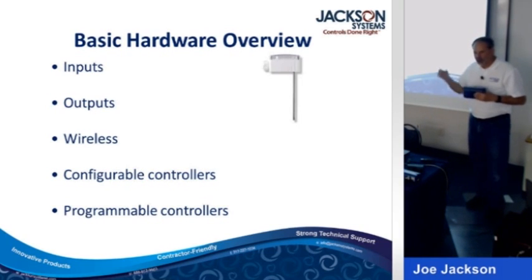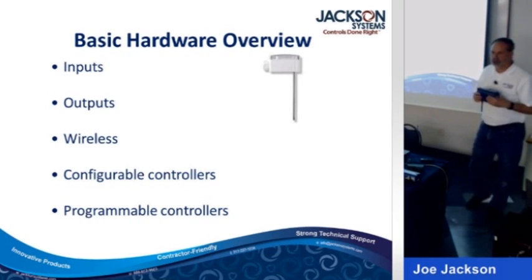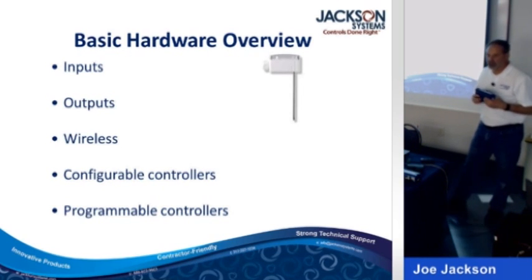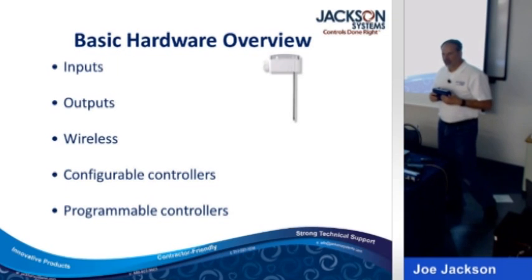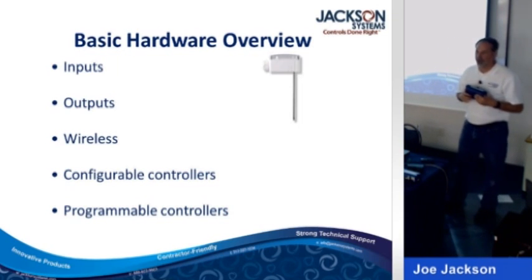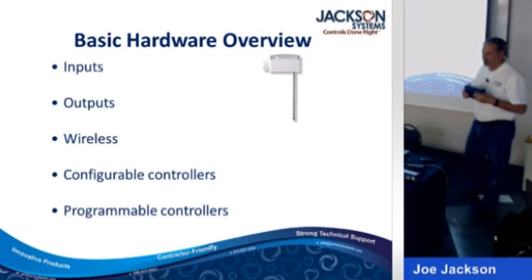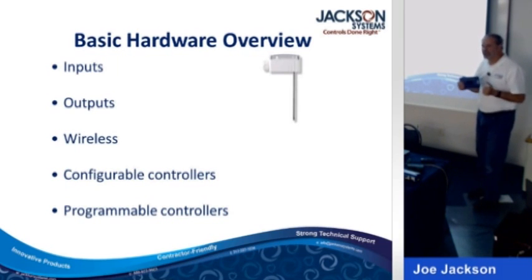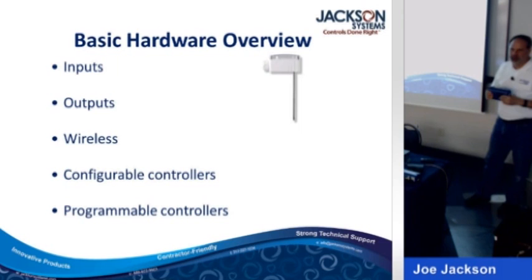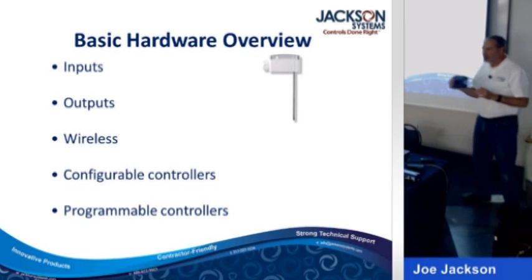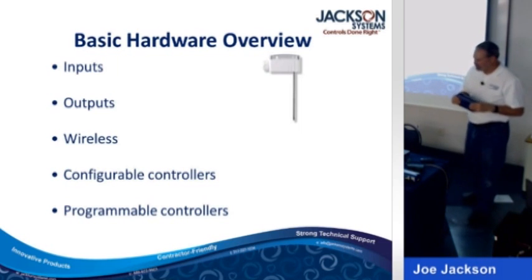I can tell you that water flows through the cooling ports up to the variable frequency drive and it sweats. And now your 500-ton chiller's got a real serious problem because it's got water hanging off its variable frequency drive. So understanding what the equipment's really supposed to do is definitely the hard part. Programming is not the hard part.